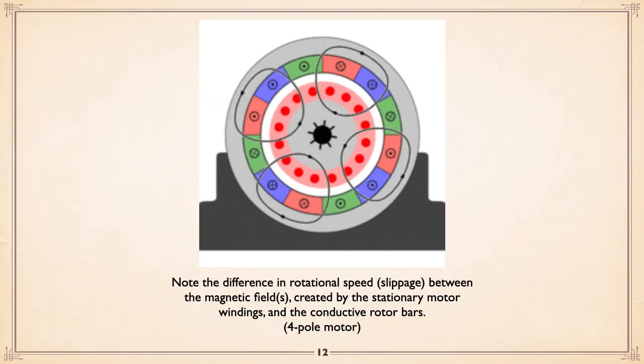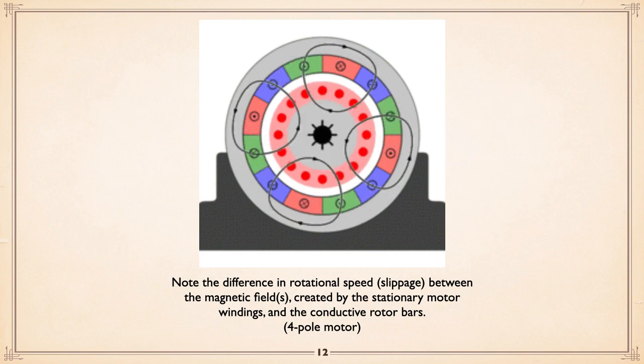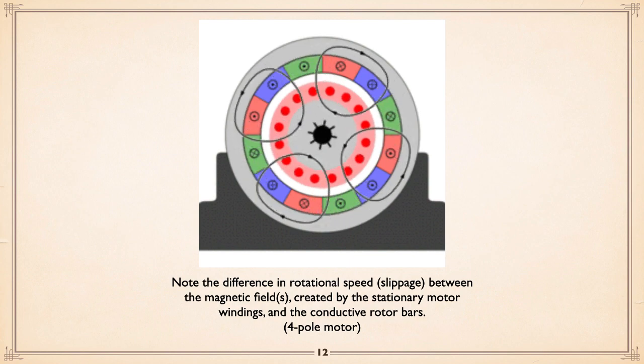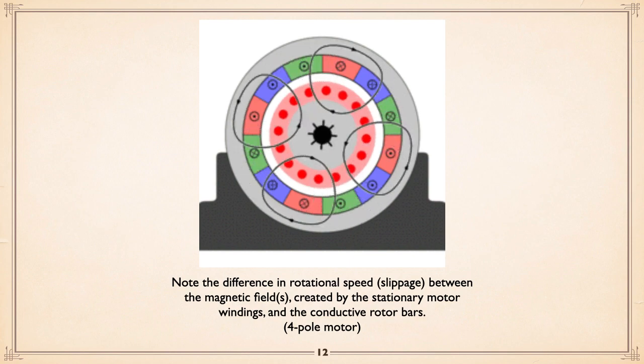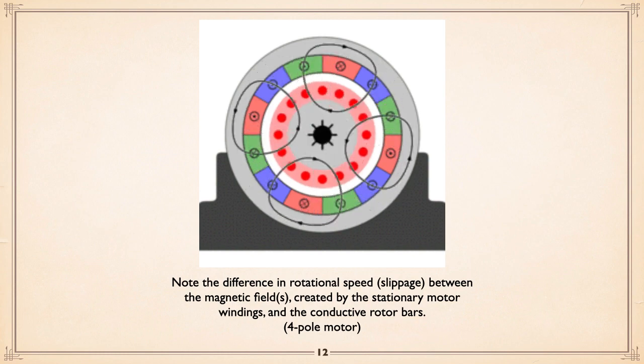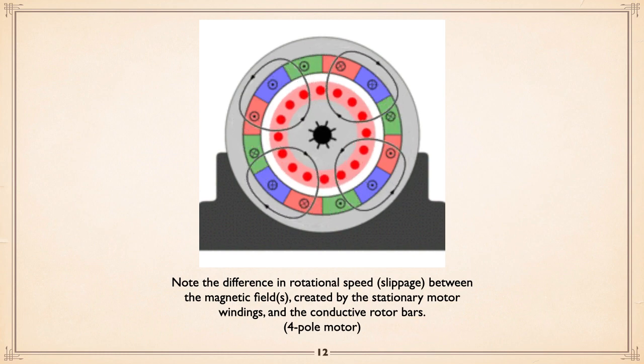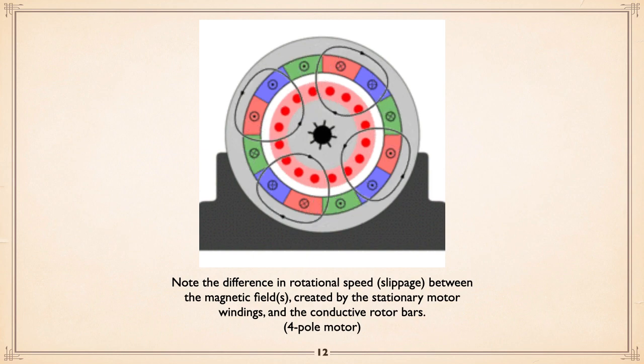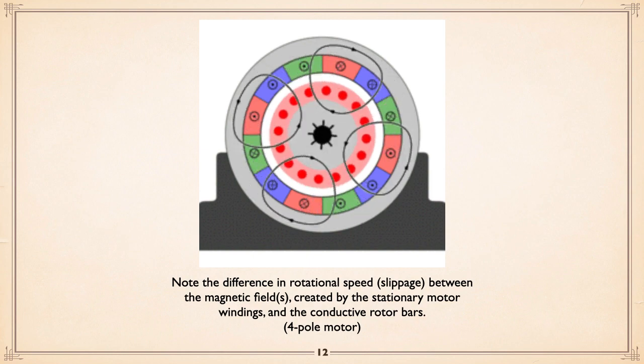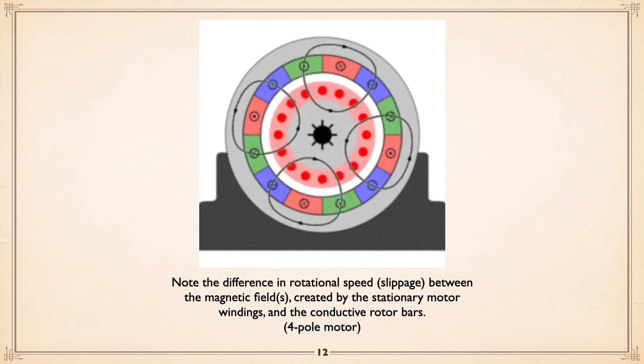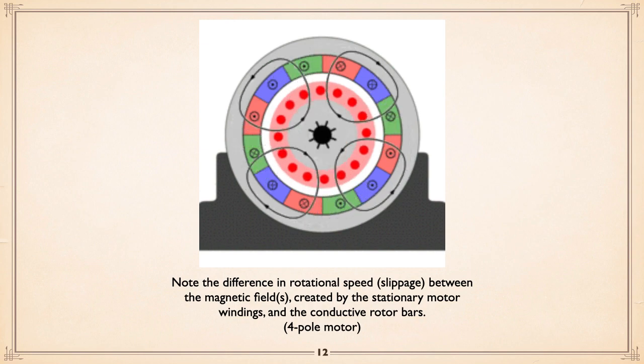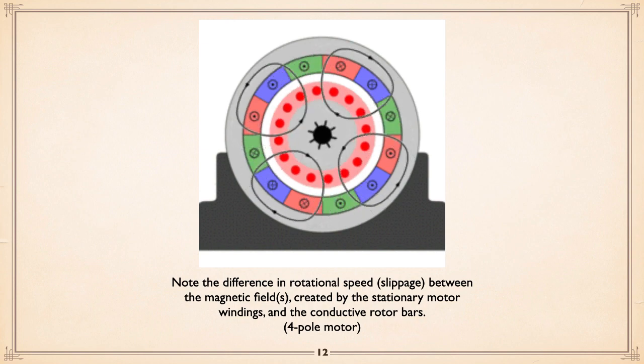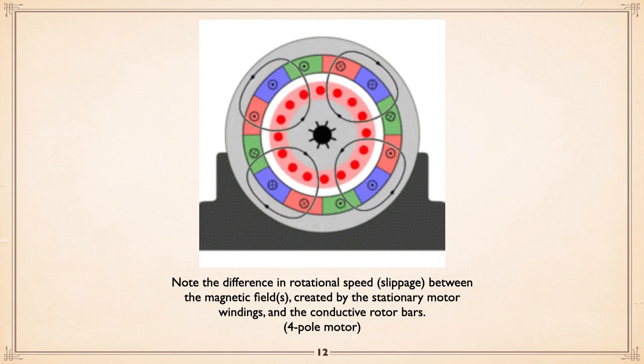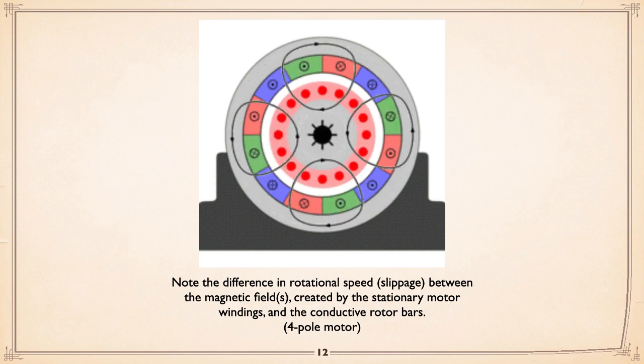This is a real good little drawing here because you can see, again, a four-pole motor, and it's turning clockwise. The magnetic field is going around, but if you look at it, just keep your eyes within one of the field, you notice that the rotor is running a little bit slower. It has to in order to generate power on those rotor bars, which generates a magnetic force. So that's why you have slippage.